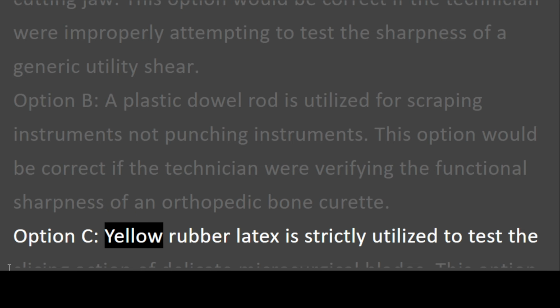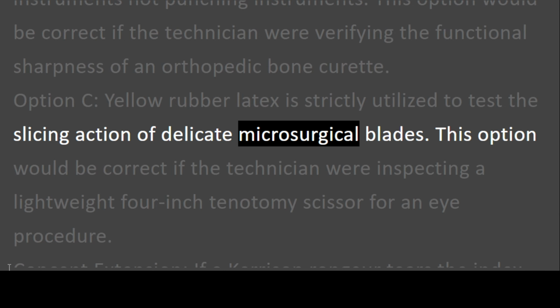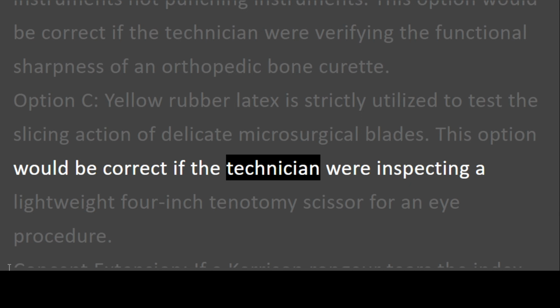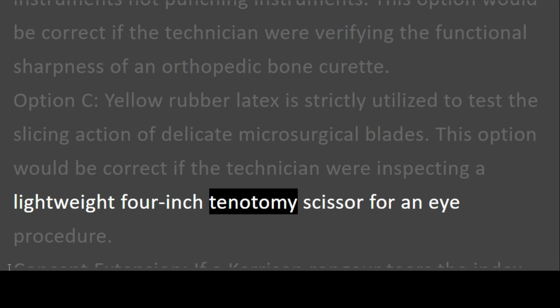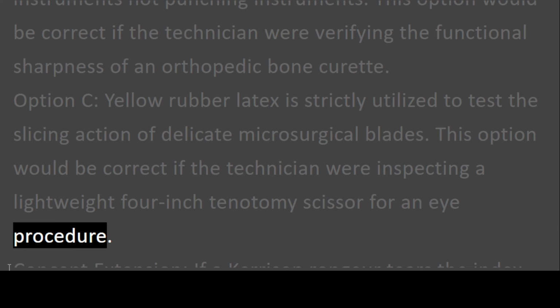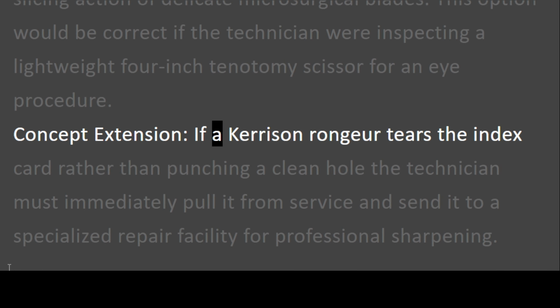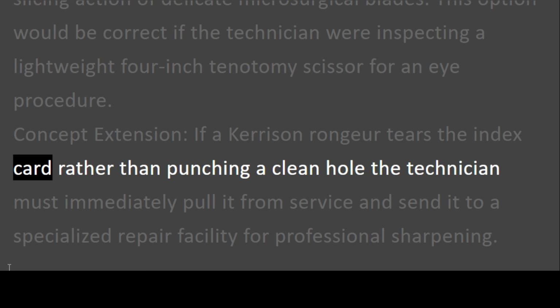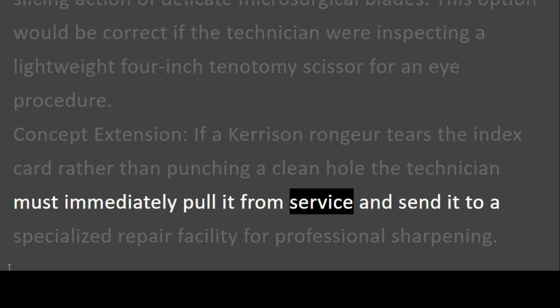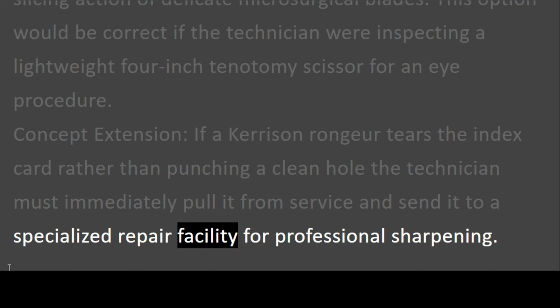Option C. Yellow rubber latex is strictly utilized to test the slicing action of delicate microsurgical blades. This option would be correct if the technician were inspecting a lightweight 4-inch tenotomy scissor for an eye procedure. Concept extension. If a rongeur tears the index card rather than punching a clean hole, the technician must immediately pull it from service and send it to a specialized repair facility for professional sharpening.